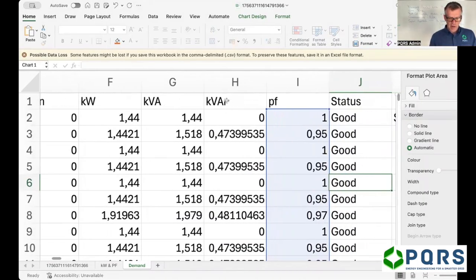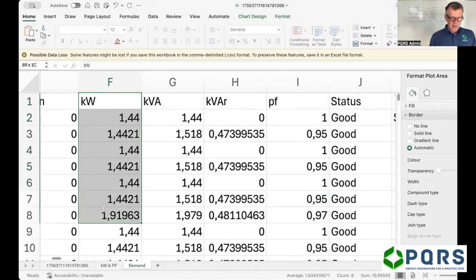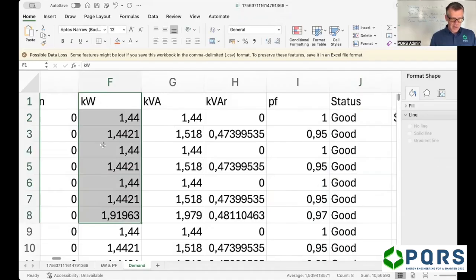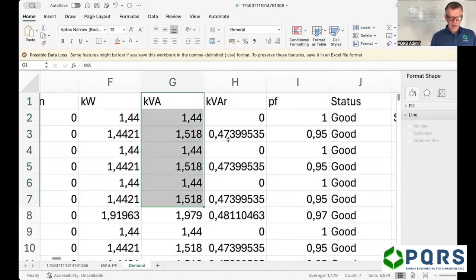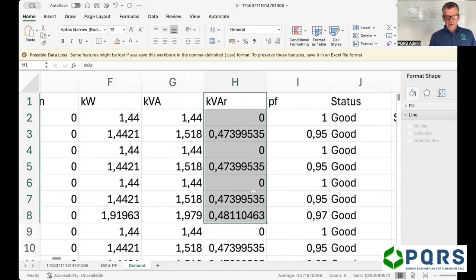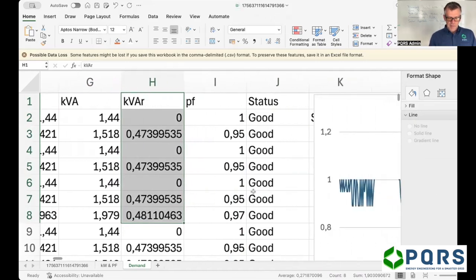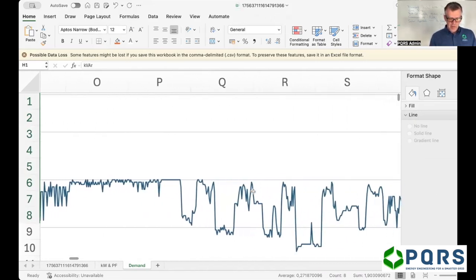They give us a power factor, which is what I took, and they give us kVA. So I took the power factor and the kVA and calculated the kilowatts. Then, because I knew the kilowatts and the kVA, I could calculate the reactive power component. And that's what we've got over here.